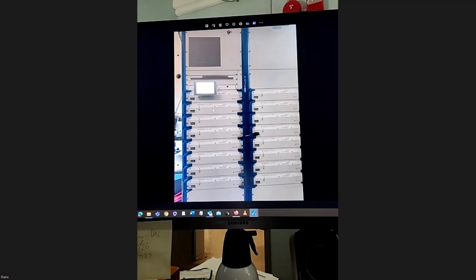What happens is if there's a problem, you undo the screw here, you undo the screw here, you go around the back, you turn off the two valves that are there, and you literally pull the drawer out. It just comes right out with cooling water still inside it, by the way, but it's sealed in. They will send you a loaner unit, you put it in, the reverse of what you do takes 2.5 minutes, and you're back up to full power.